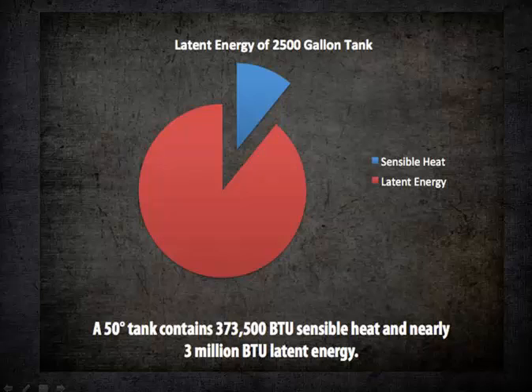Yeah. So to get another representation of how much energy is in that tank, a 50-degree tank that's 2,500 gallons, which I didn't say on here, but that's what we were referring to. Again, it would be 20,750 pounds of water, which is 20,750 BTUs per degree. So if you take 50 degrees minus 32, you have 18 degrees of energy from 50 to 32. That represents 373,500 BTUs. And then when you hit 32 degrees is where you've got almost 3 million.